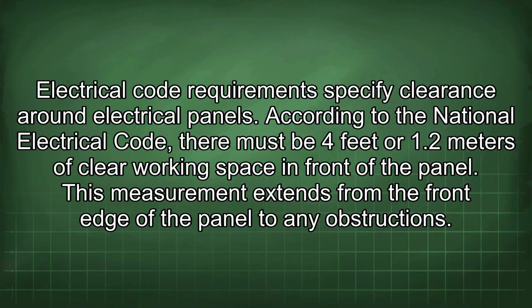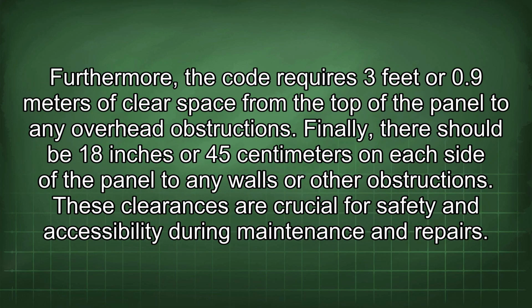Electrical code requirements specify clearance around electrical panels. According to the National Electrical Code, there must be 4 feet or 1.2 meters of clear working space in front of the panel. This measurement extends from the front edge of the panel to any obstructions. Furthermore, the code requires 3 feet or 0.9 meters of clear space from the top of the panel to any overhead obstructions. Finally, there should be 18 inches or 45 centimeters on each side of the panel to any walls or other obstructions. These clearances are crucial for safety and accessibility during maintenance and repairs.